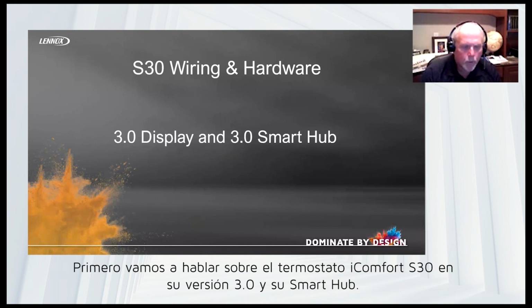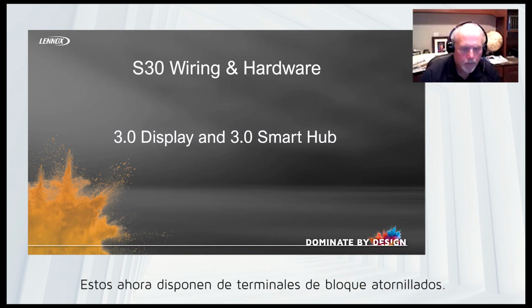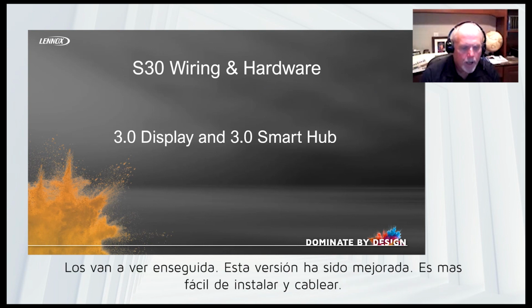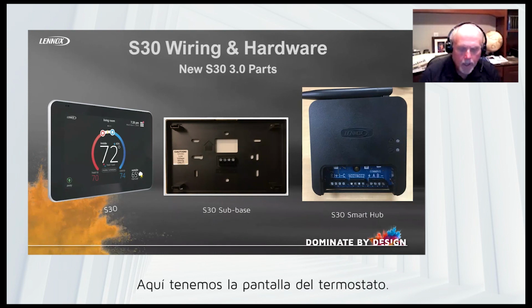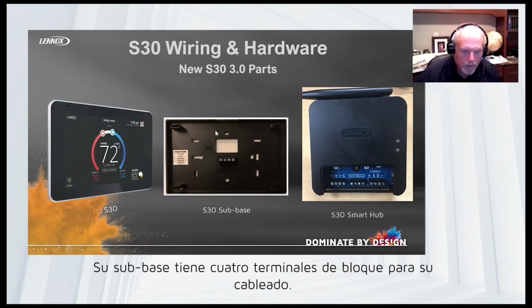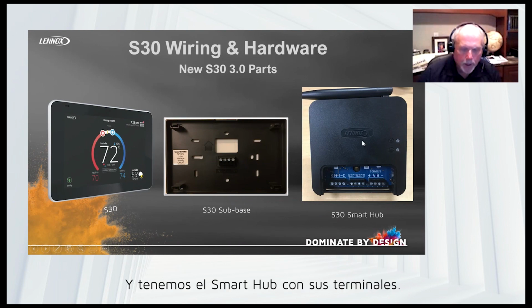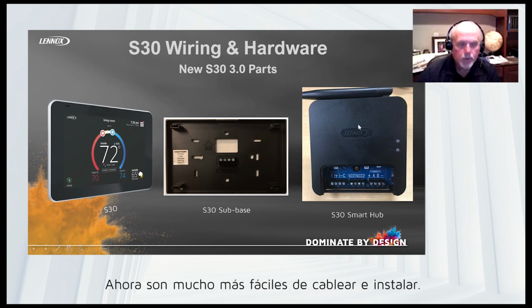Okay, so S30, wiring and hardware. We are going to look at the 3.0 display and 3.0 Smart Hub. These have screw lug terminals, which I'll show you here in just a minute. They have been upgraded to that, which makes it a much better product, much easier to wire and install. So here we have the display, and we have our sub base here, which has 4 screw lug terminals for your wiring. And we have the Smart Hub, which also has screw lugs for wiring. Makes it a much easier way to wire up and install.